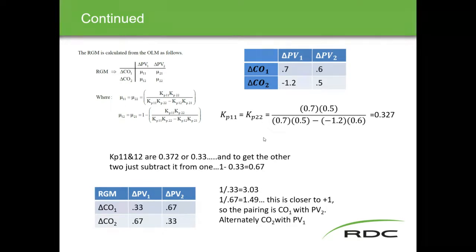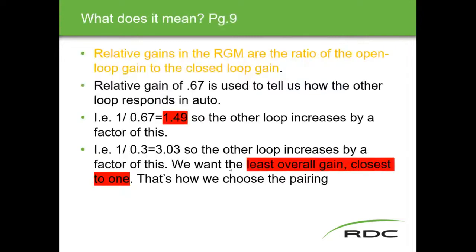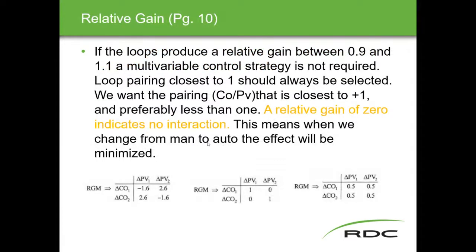It's really another week's worth of a course to get into that depth. Our expectations here are to distinguish the severity of interaction. Relative gains in the matrix are the ratio of the open loop gain to the closed loop gain. If we do that map, the other loop increases by one factor, and the other one increases by another factor. Overall we want the least gain or close to one, and that's how we end up choosing the pairing.